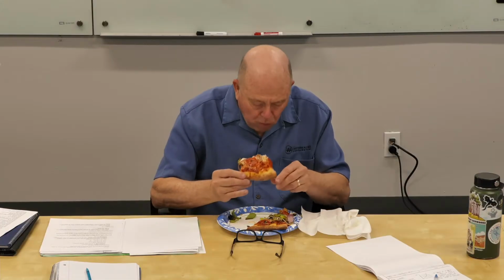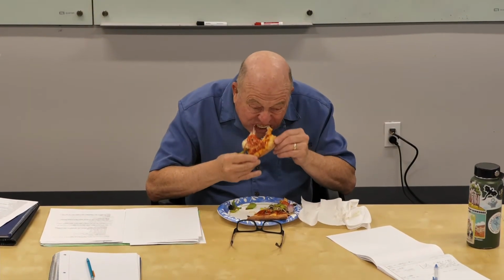Excellent. Learning anything at all? Yeah, learning about sizing a new supply fan. There's this fan we're replacing at Fox in the penthouse of building 103 with Chad. The fan wall project you're talking about? Yes. We know the design conditions, we know it needs to be 4.5 inches of static. And it's at 100,000 CFM for the supply fan, so we're replacing it with a fan wall. Yes, sir.